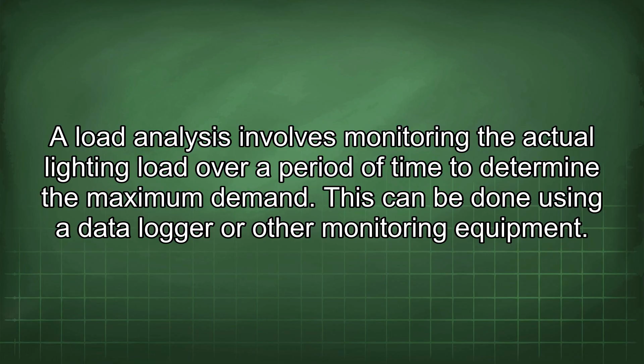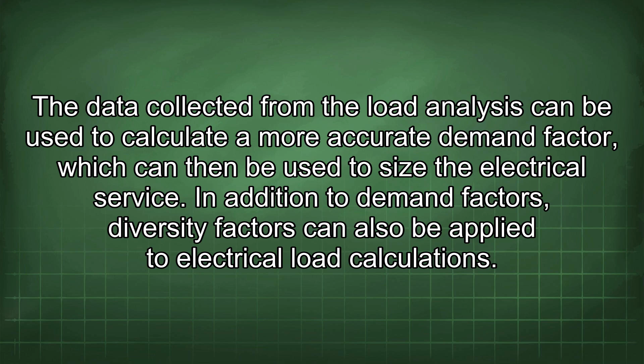The data collected from the load analysis can be used to calculate a more accurate demand factor, which can then be used to size the electrical service. In addition to demand factors, diversity factors can also be applied to electrical load calculations.